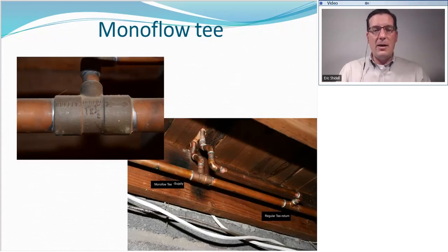Here's some monoflow T's in real life. You can see the T here, and it's actually labeled supply, and it has an arrow on it, which means this is the direction of flow, and there's that little branch line. So here we have that main coming along, and it branches off, goes up to the emitter, goes through the emitter, comes back, and rejoins the main as such. So that's the basic idea.